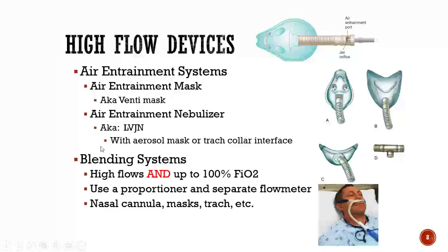You'll also look at blending systems — the O2 blender. In some hospitals that have only one source gas, it's an oxygen blender that entrains its own room air. The flow meter can go up to 75 liters per minute or higher, and the proportioner can be set from 21% all the way up to 100%. Interfaces include high flow nasal cannulas, masks, and trachs.